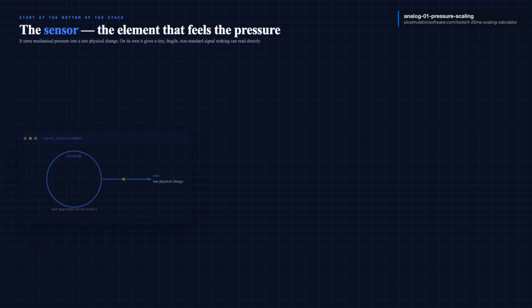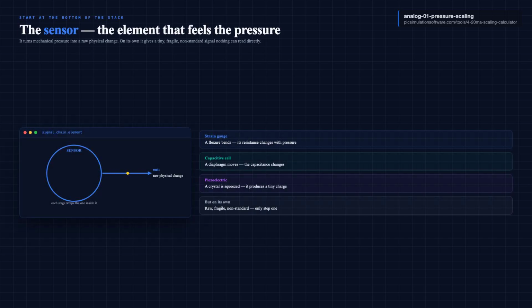Now, back to the sensing element. Start at the very bottom of the stack. The sensor. This is the element that physically responds to pressure. There are a few common types. A strain gauge bends, and its resistance changes. A capacitive cell moves a diaphragm, and the capacitance changes. A piezoelectric crystal gets squeezed, and it produces a tiny charge. Whatever the type, the job is the same. Turn mechanical pressure into some raw physical change. But here's the catch. On its own, that raw element gives you a tiny, fragile, non-standard output. Nothing on the floor can read it directly. So the sensor is real, and it is essential, but it is only step one.